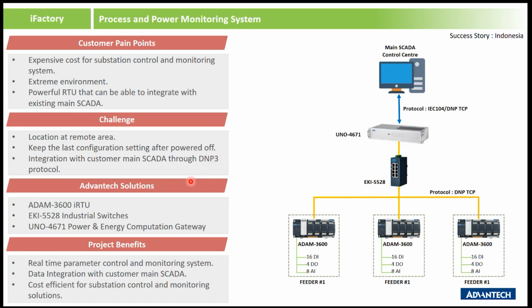So how can we do this? We spec'd in the collection module Adam 3600, which can collect data from the I/O — for example, 16 DI, 4DO, 8AI — and then send out the data using DNP3 protocol, which complies with customer requirements.